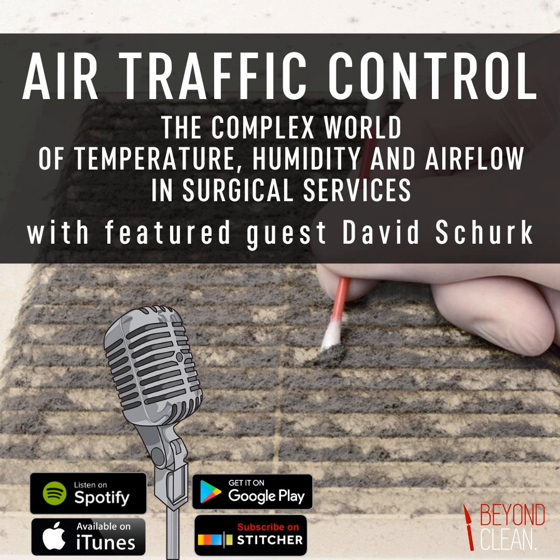The coils can load up with dirt if the filters aren't clean, and of course that creates the perfect breeding ground for mold. So I see that, I won't say every hospital I go into, but I will say a majority of the hospitals that I go into have some type of an issue like that occurring in their HVAC systems. And these HVAC systems, of course, serve every square foot of hospital facility.